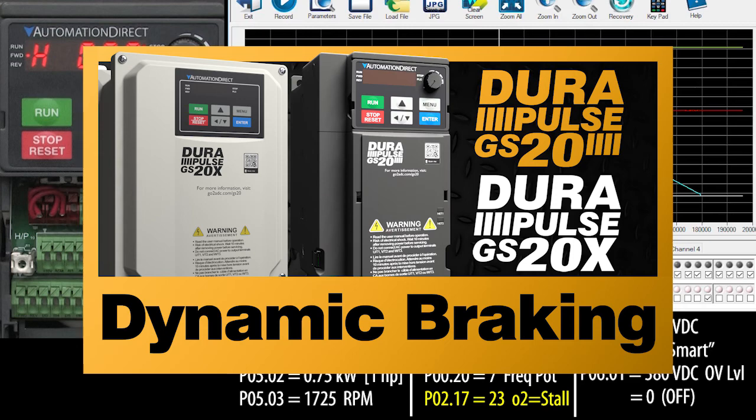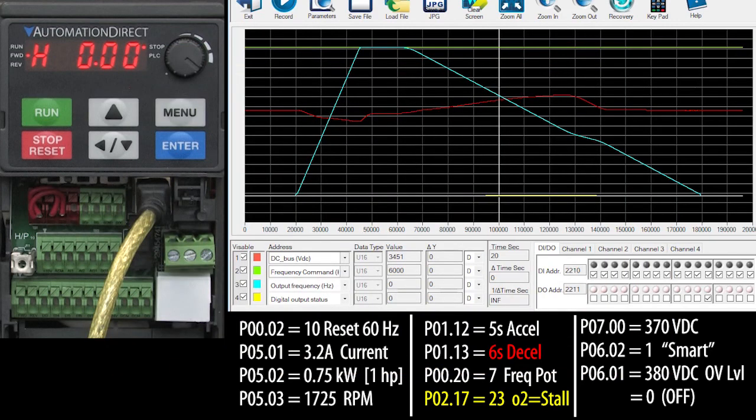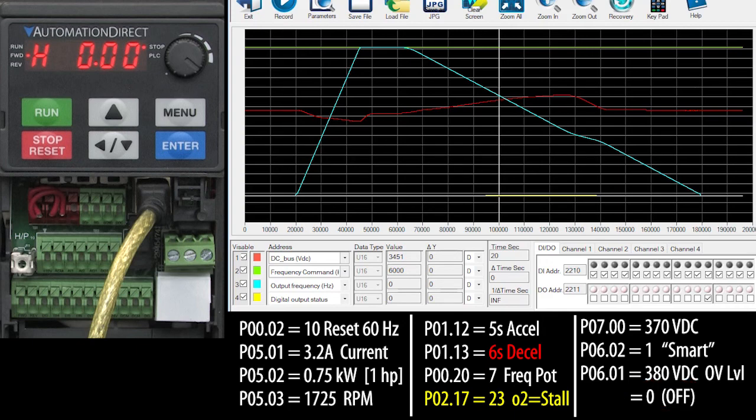If you do use dynamic braking, be sure to turn off these stall prevention methods by setting parameter 6.01 to a zero. That way they won't interfere with your dynamic braking.